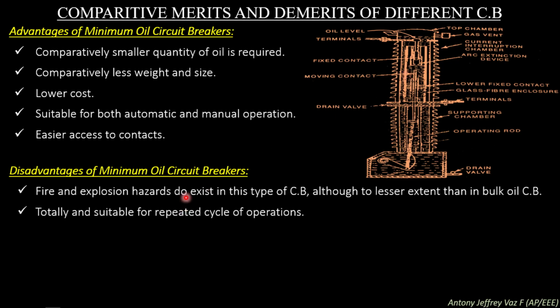Totally unsuitable for repeated cycles of operation. Since only a small quantity of oil is present in the arcing chamber, severe or repeated operation of a minimum oil circuit breaker is not suitable and it cannot be used in such power systems. Requires more frequent inspections and replacement of oil.